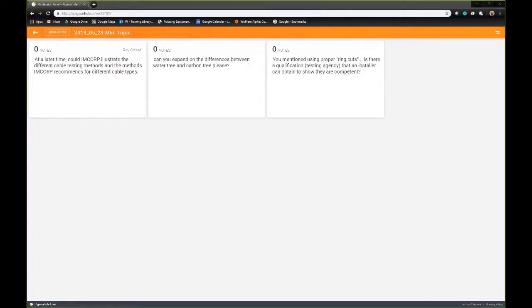When we went out there and we showed the guys, over and over, we would test the cable, there's partial discharge there, and we would look at that cable with them together, and show them where it wasn't a proper ring cut, or where there might have been some contamination, or where the ring cut was too deep, or it had a little point on it.